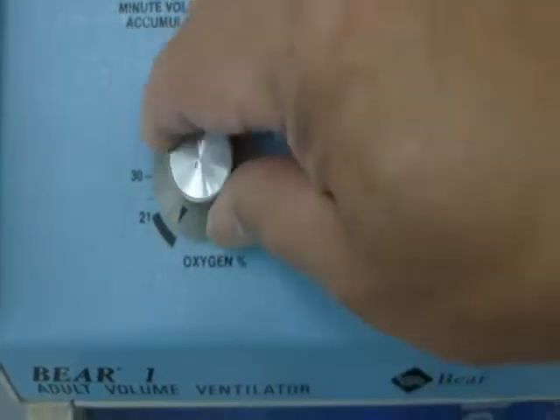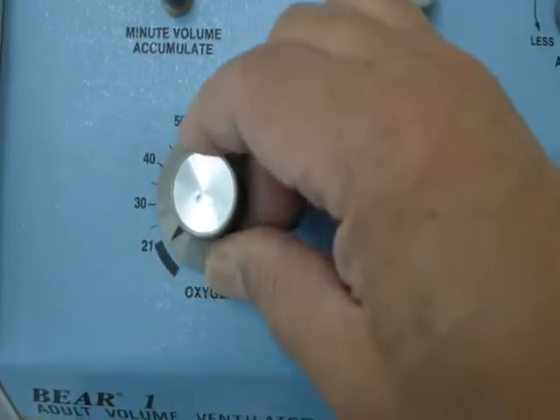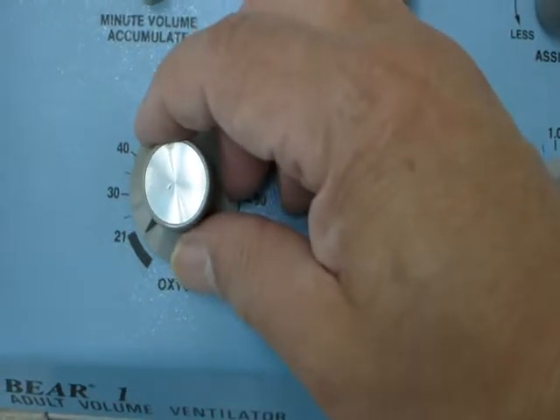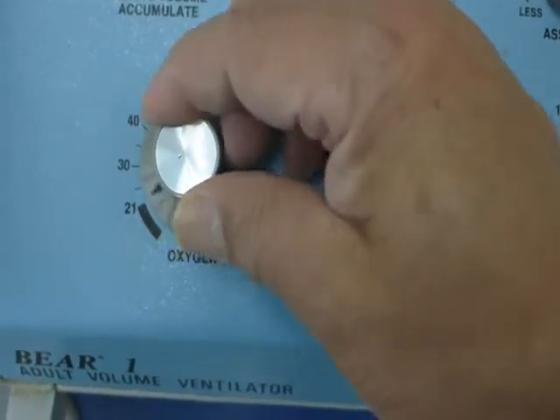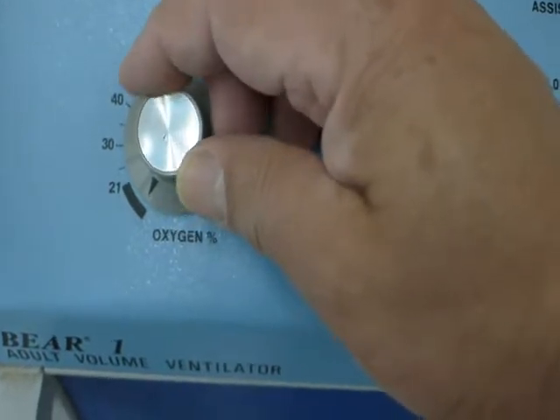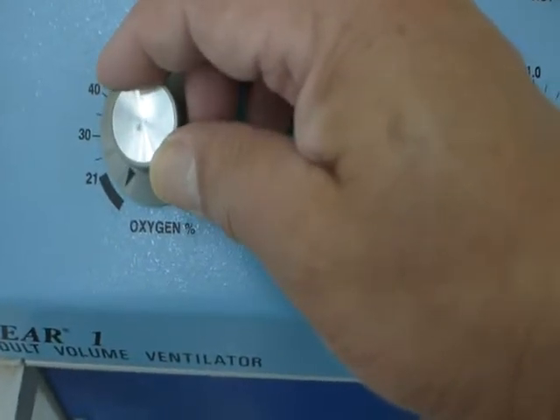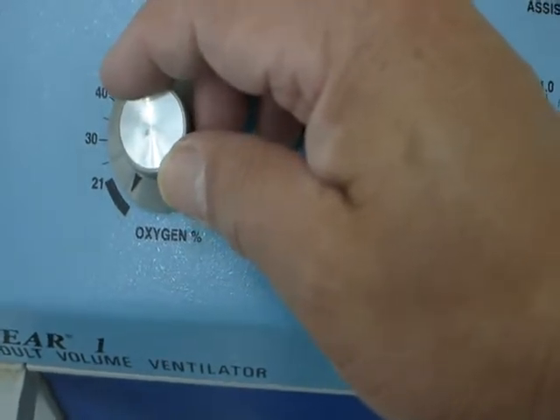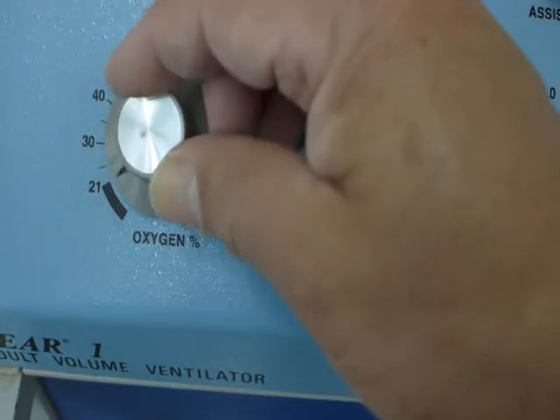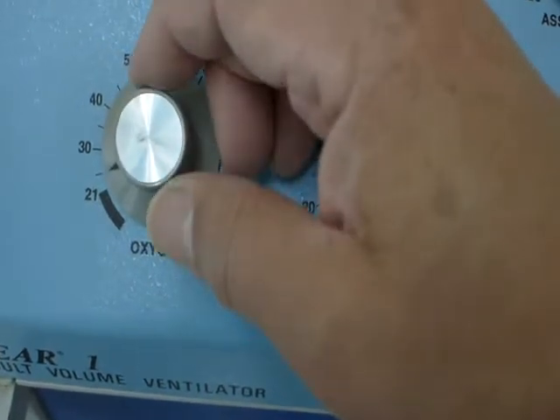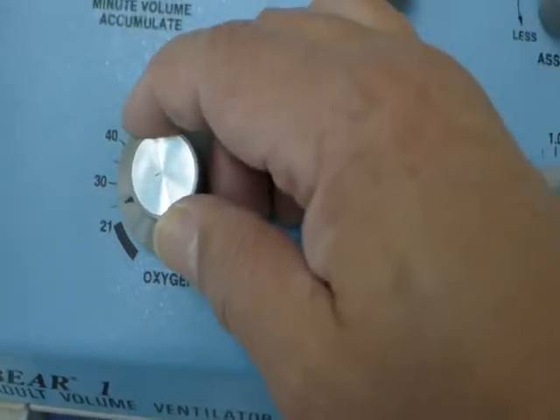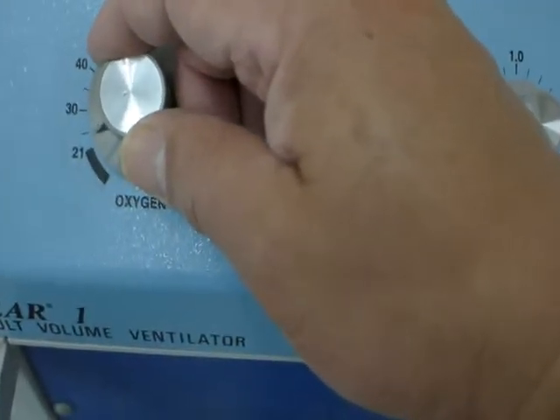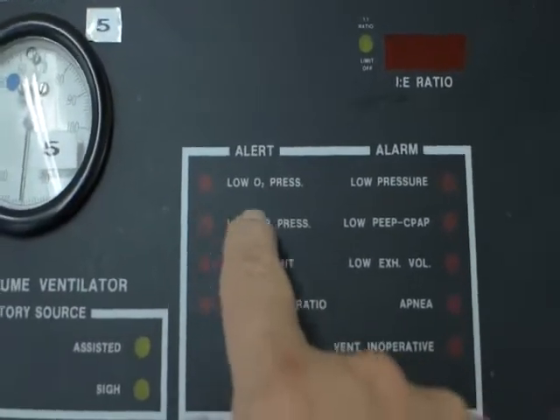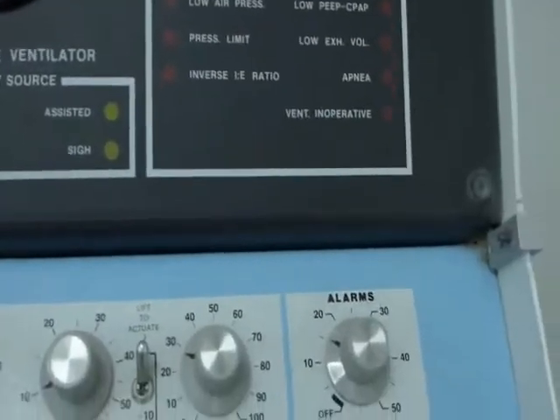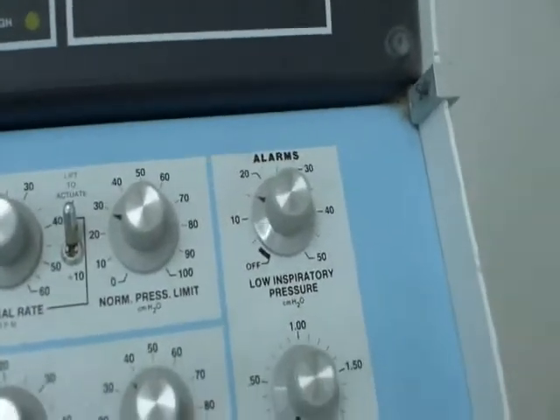So we see this one. This is the oxygen blender, or FiO2, fractional inspired oxygen. Normally we run this from the air compressor, and we would like to keep this one at 21. If you don't have oxygen and we set this above 21%, the low oxygen pressure alarm is going to alarm. We will see the low oxygen pressure alarm somewhere around here. So we keep this one at 21%.